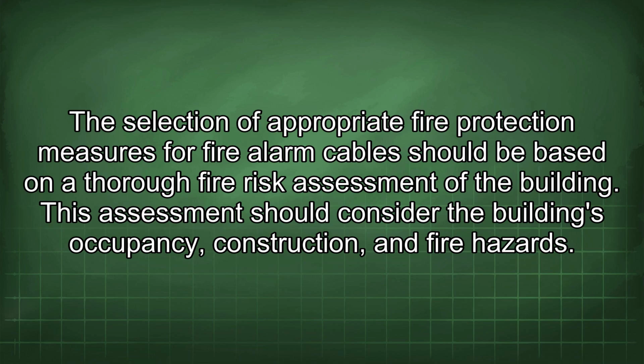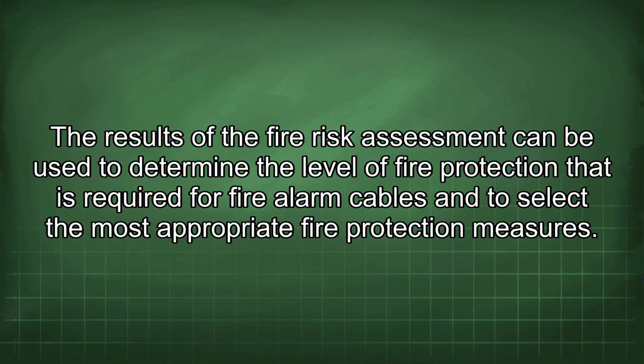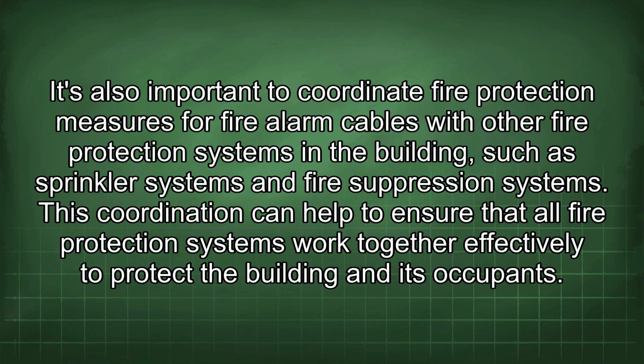The selection of appropriate fire protection measures for fire alarm cables should be based on a thorough fire risk assessment of the building. This assessment should consider the building's occupancy, construction, and fire hazards. The results of the fire risk assessment can be used to determine the level of fire protection that is required for fire alarm cables and to select the most appropriate fire protection measures. It's also important to coordinate fire protection measures for fire alarm cables with other fire protection systems in the building, such as sprinkler systems and fire suppression systems.